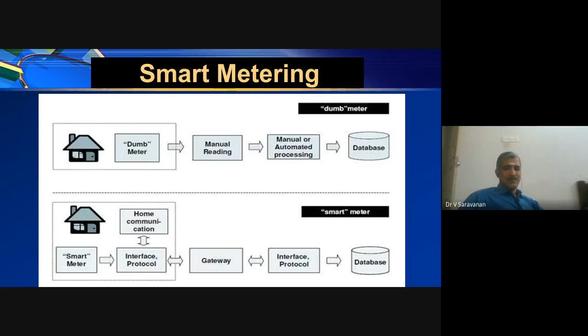There are four types of smart meters. The first developed is local automated meter reading, called AMR. The second is remote automated meter reading, where the meter is accessed at remote locations. The third is the net meter, used wherever you go for a grid-tie solar PV system. Finally, there's the network meter or advanced metering infrastructure.